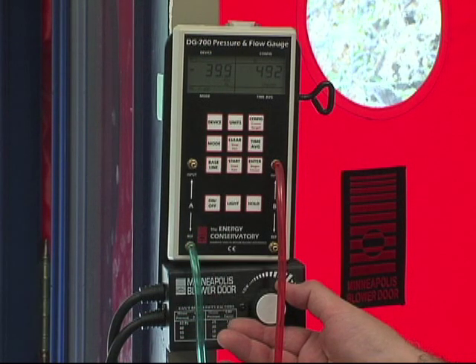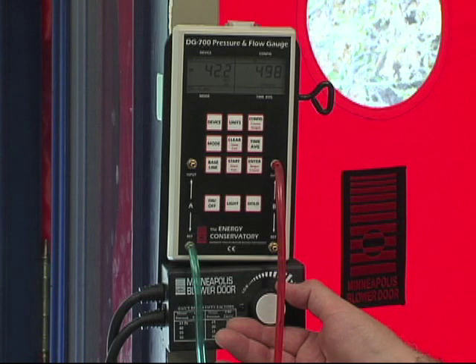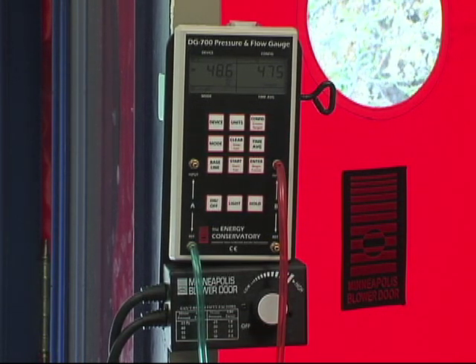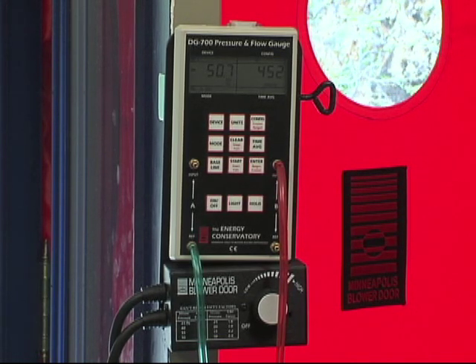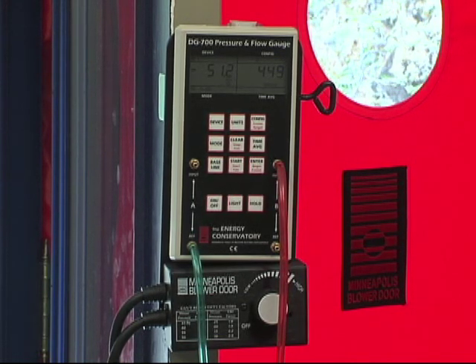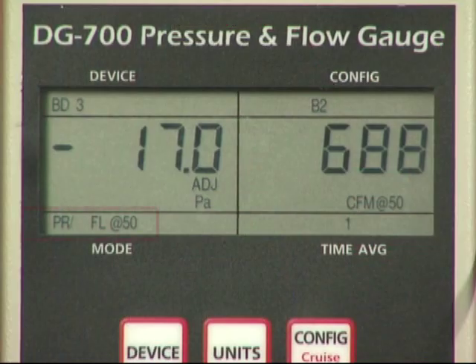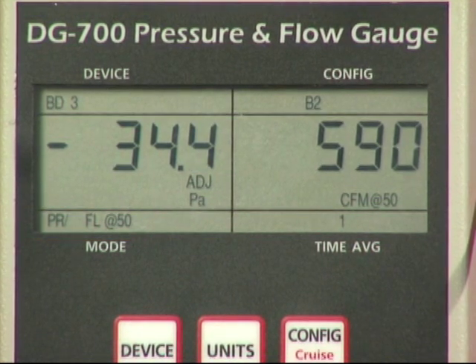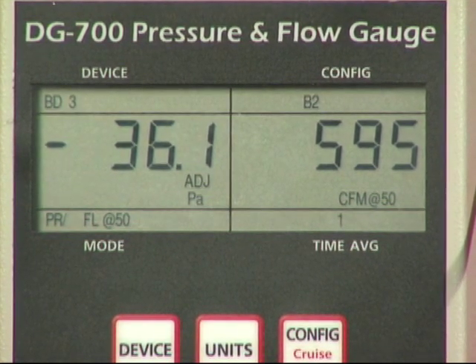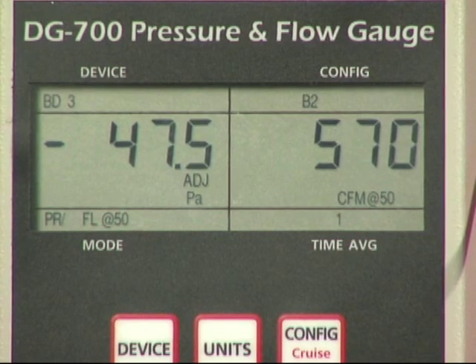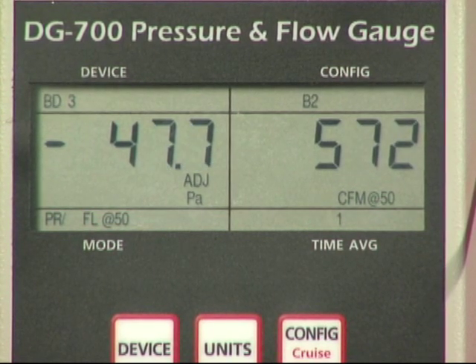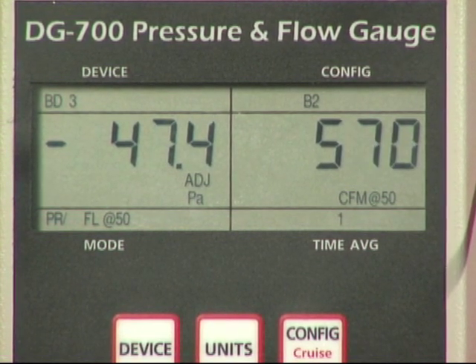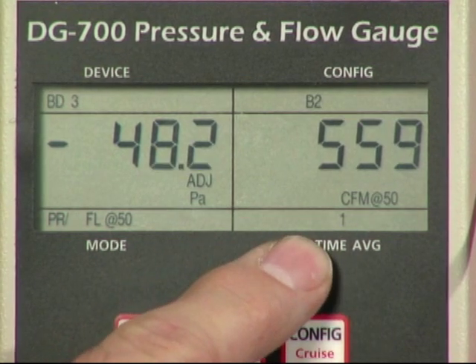We're ready to make the final adjustments to the fan speed. Continue to increase the fan speed until the building depressurization shown on channel A is between negative 45 and negative 55 pascals. Just get close to the target pressure and make your measurement. As long as you're using the PRFL at 50 mode and the test pressure displayed on channel A is within 5 pascals of the minus 50 pascal target pressure, any errors introduced by estimating the leakage on channel B will typically be very small — usually less than 1%. Channel B will now display the one-point CFM50 leakage estimate.